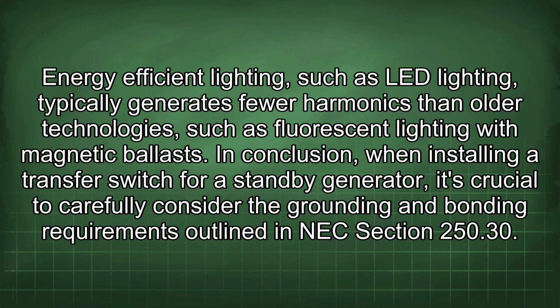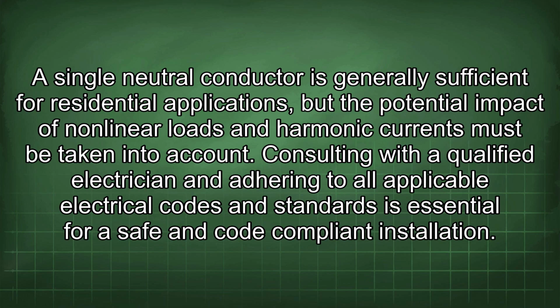In conclusion, when installing a transfer switch for a standby generator, it's crucial to carefully consider the grounding and bonding requirements outlined in NEC Section 250.30. A single neutral conductor is generally sufficient for residential applications, but the potential impact of nonlinear loads and harmonic currents must be taken into account. Consulting with a qualified electrician and adhering to all applicable electrical codes and standards is essential for a safe and code-compliant installation.